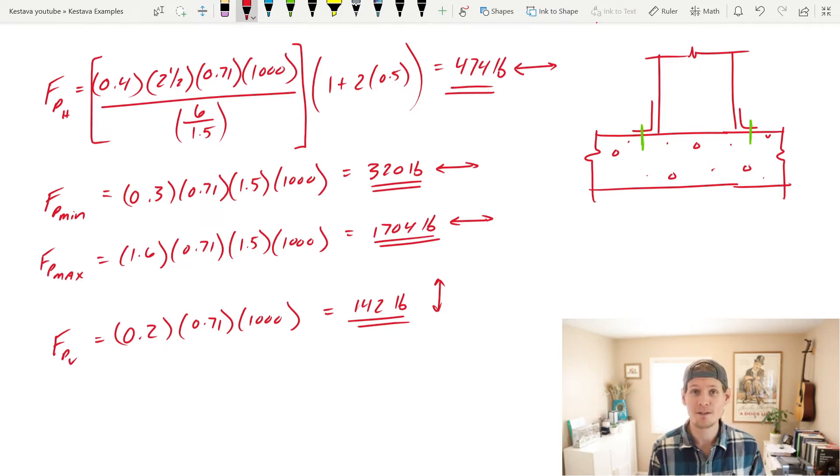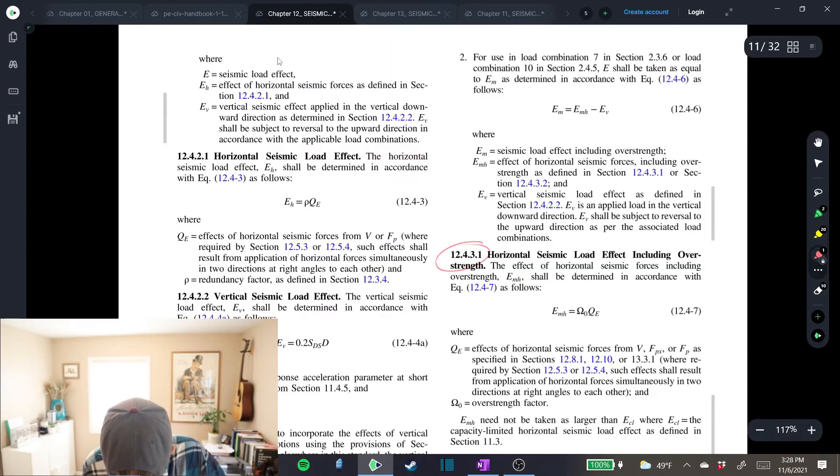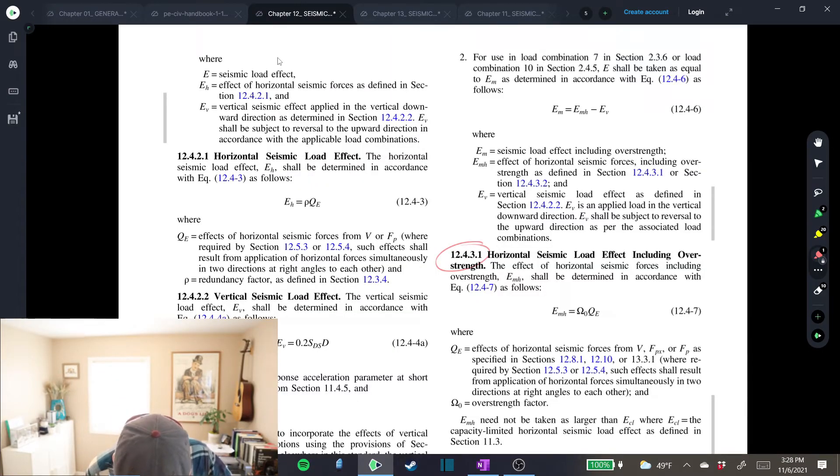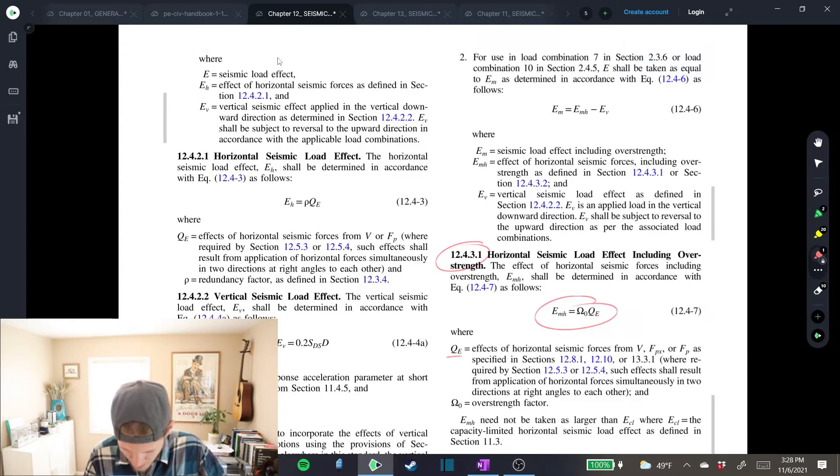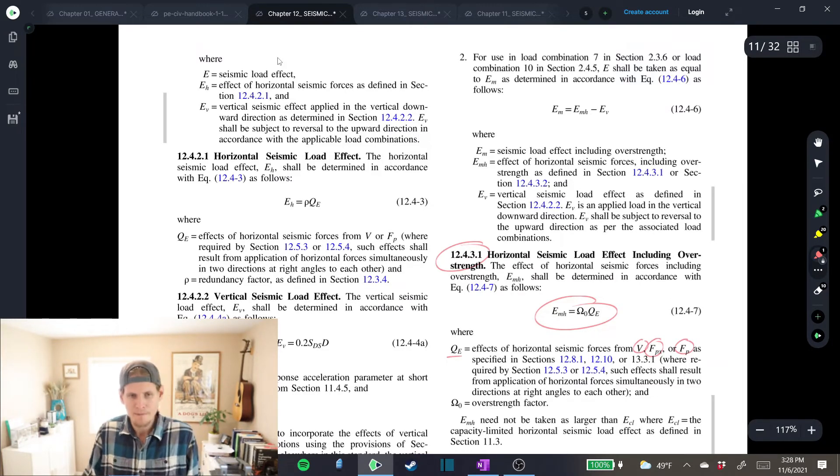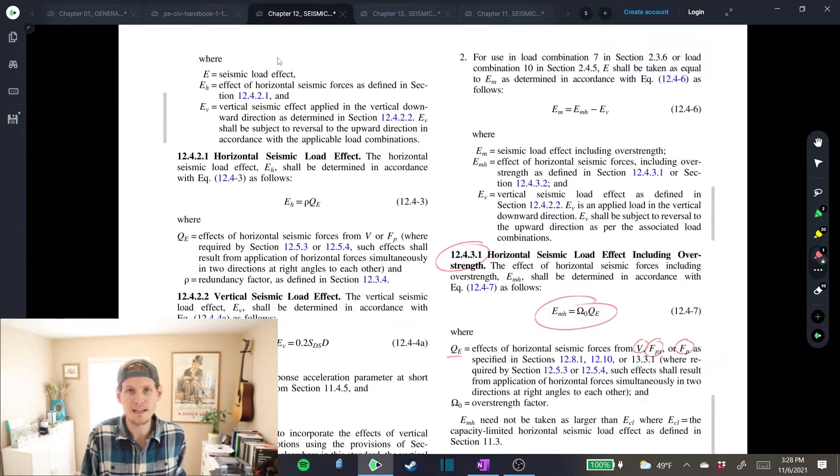Okay, so let's jump over to chapter 12.4 to further refine our loading criteria. We land ourselves here, and we want horizontal seismic load effects, including overstrength. That's our equation right there. And if we look at QE, QE is equal to the horizontal seismic forces of V, FPX, or FP. And that's dependent upon what analysis you're doing. Is it a building? Is it a non-building structure? Is it a structural component?